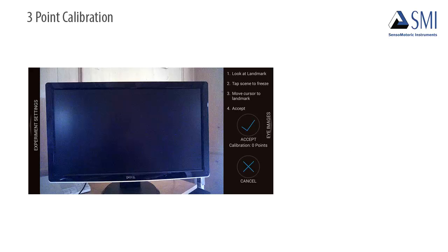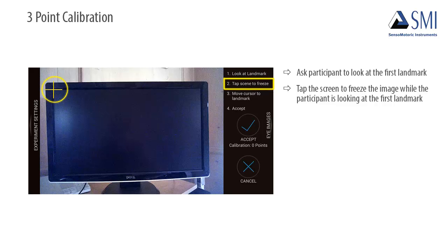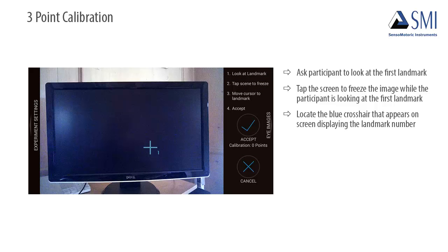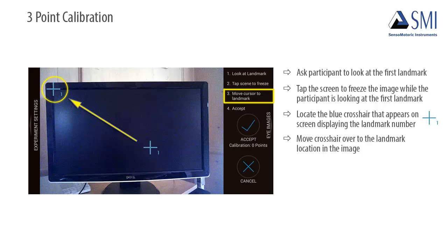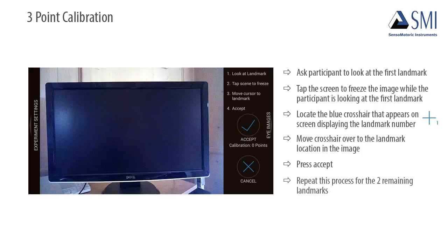To perform three-point calibration, ask the participant to look at the first landmark you have chosen. Then tap the screen to freeze the image while the participant is looking at that first landmark. Locate the blue crosshair that appears on screen displaying the landmark number, and move that crosshair over to the exact landmark location in the frozen image on the screen. Press Accept and repeat this process for the two remaining landmarks.